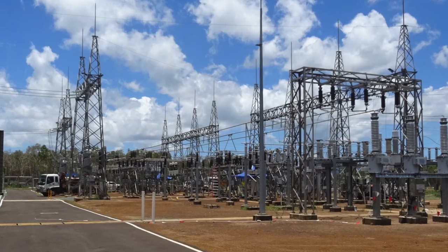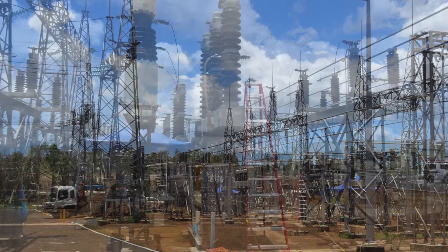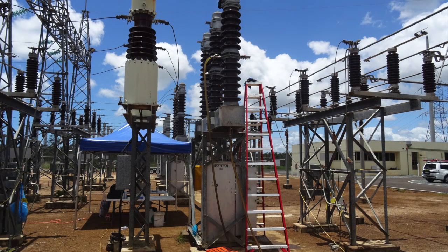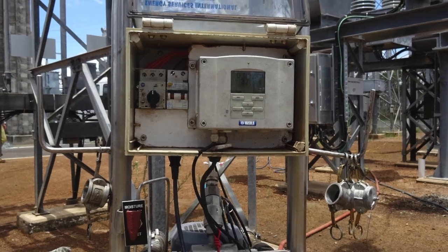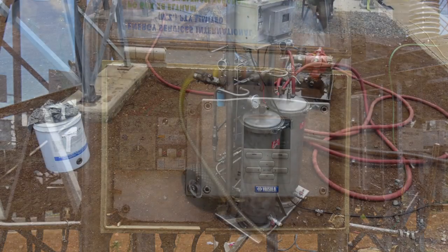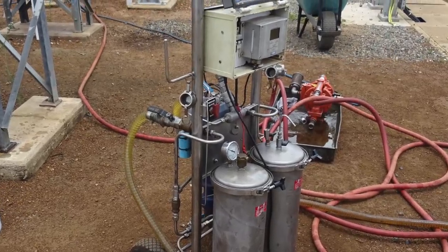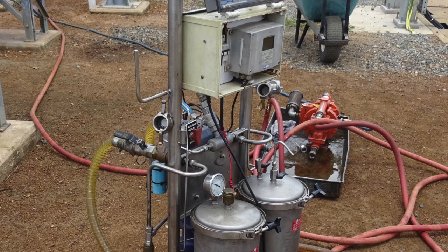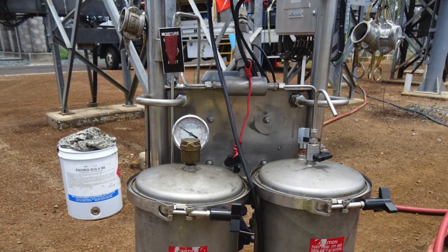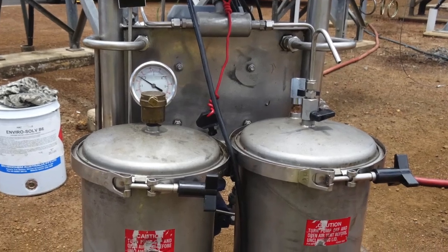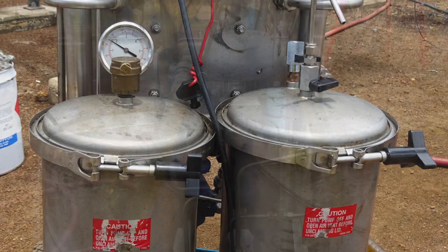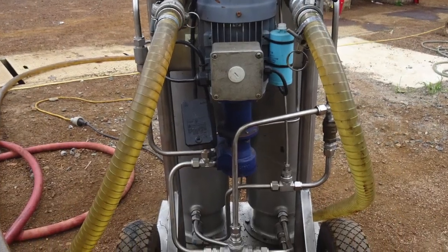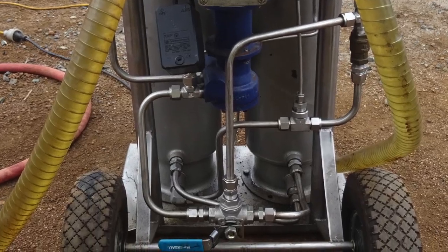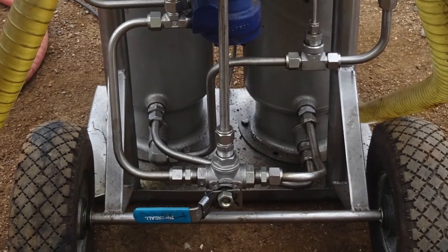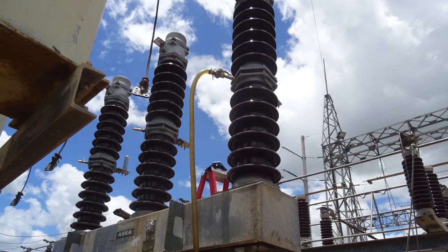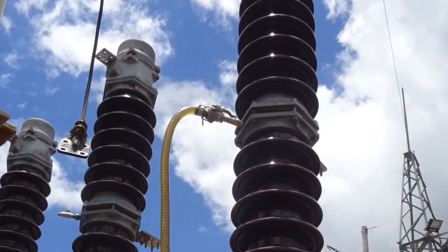To help with some of the problems we are seeing in the field with maintaining oil quality, we are currently trialling field treatment units in Mackay, Rockhampton and Maryborough. These portable trolley units can achieve flow rates of up to 1,000 litres per hour and are fitted with two separate cartridges, one to remove dissolved water to less than 10 parts per million, and the second for the removal of both particles and emulsified water. Initial reports from Mackay in relation to work on the HLC circuit breakers are promising. As the trials progress, we'll keep everyone up to date.